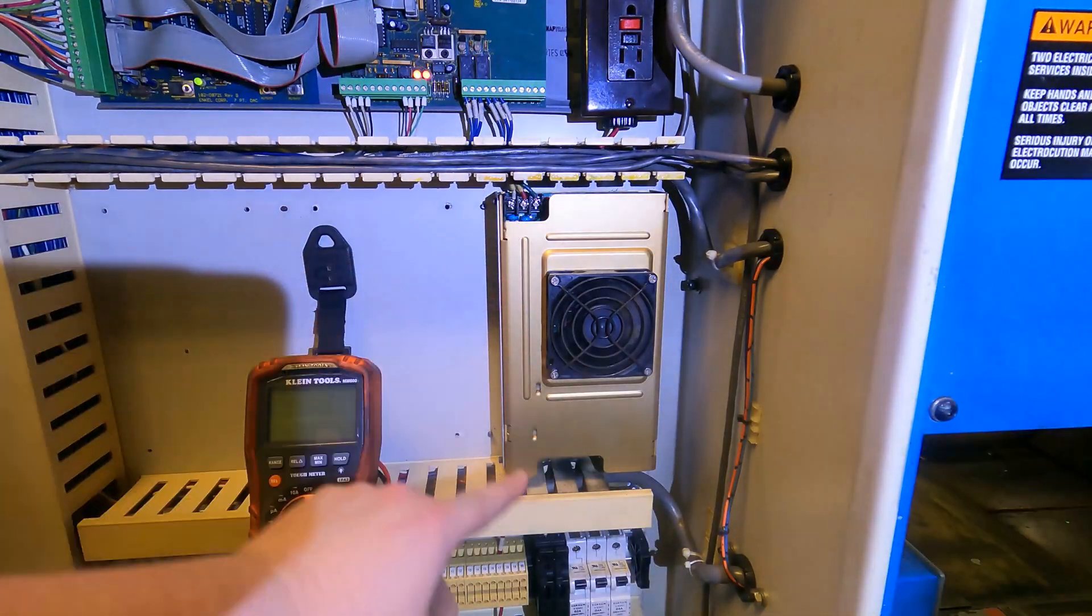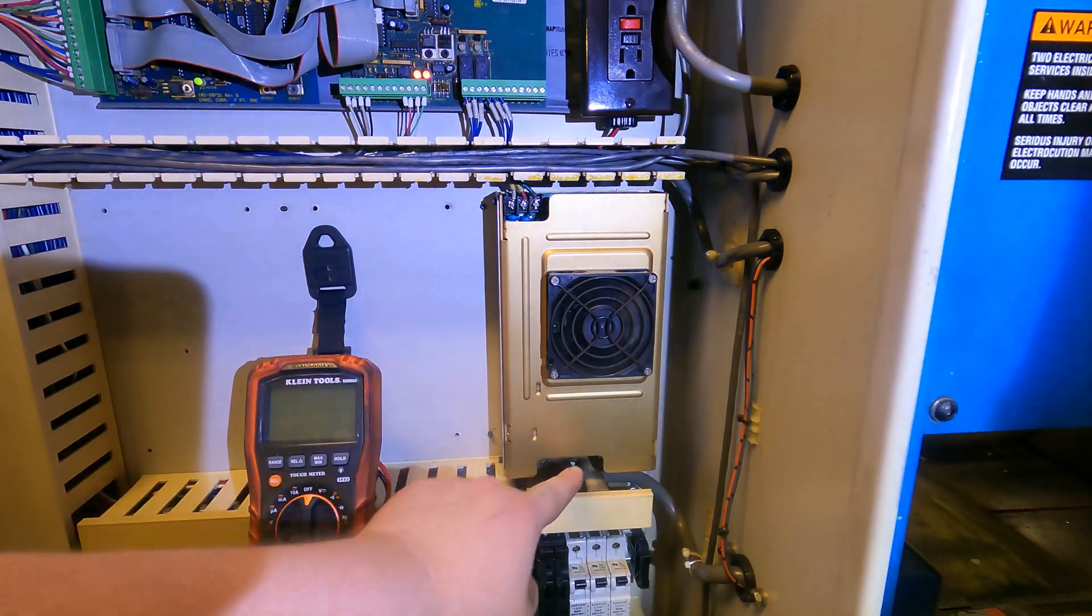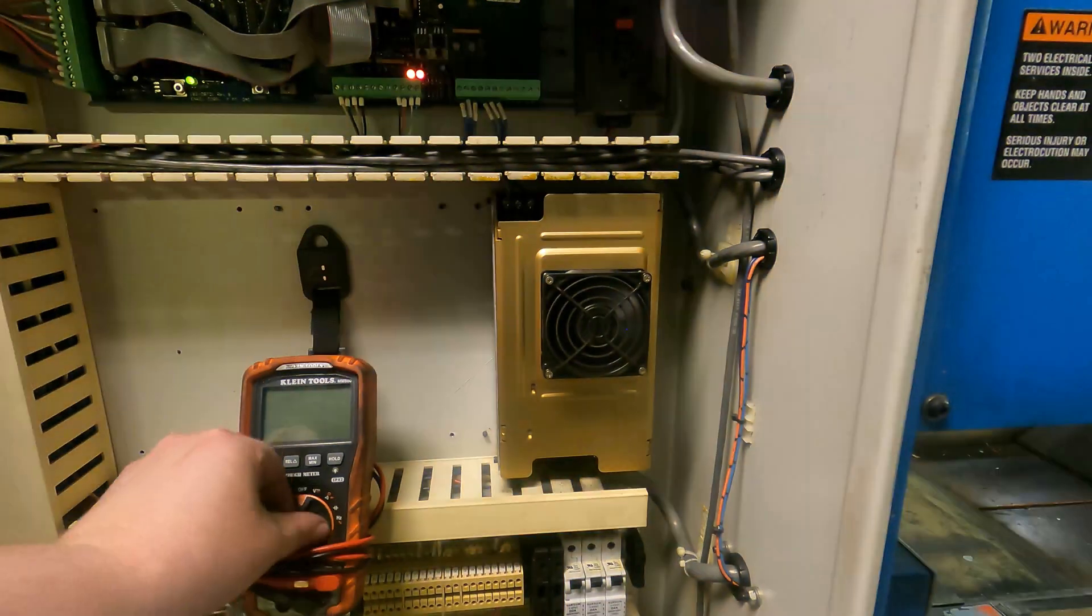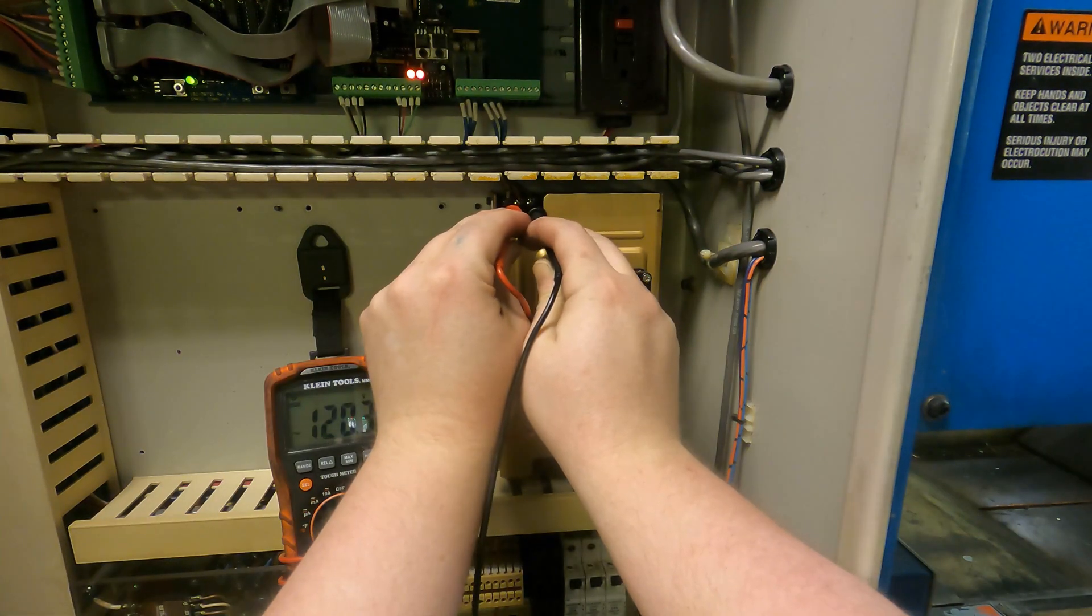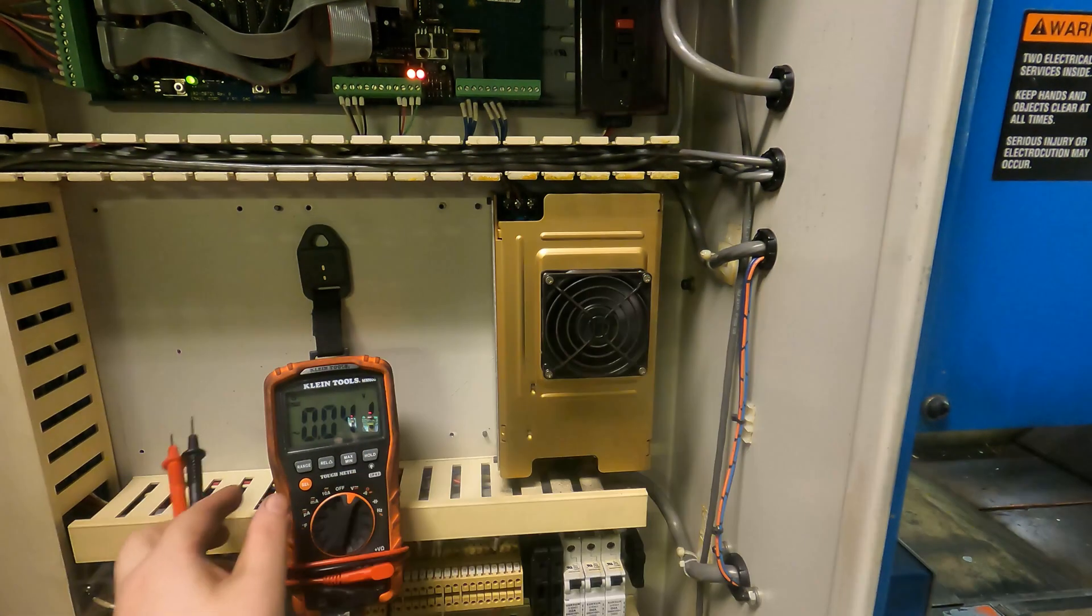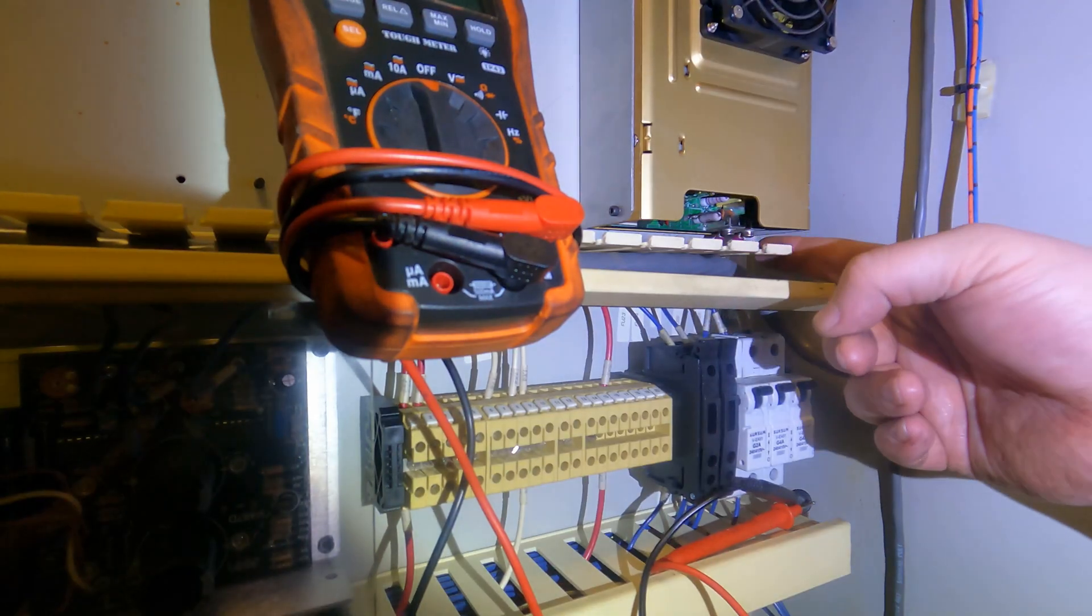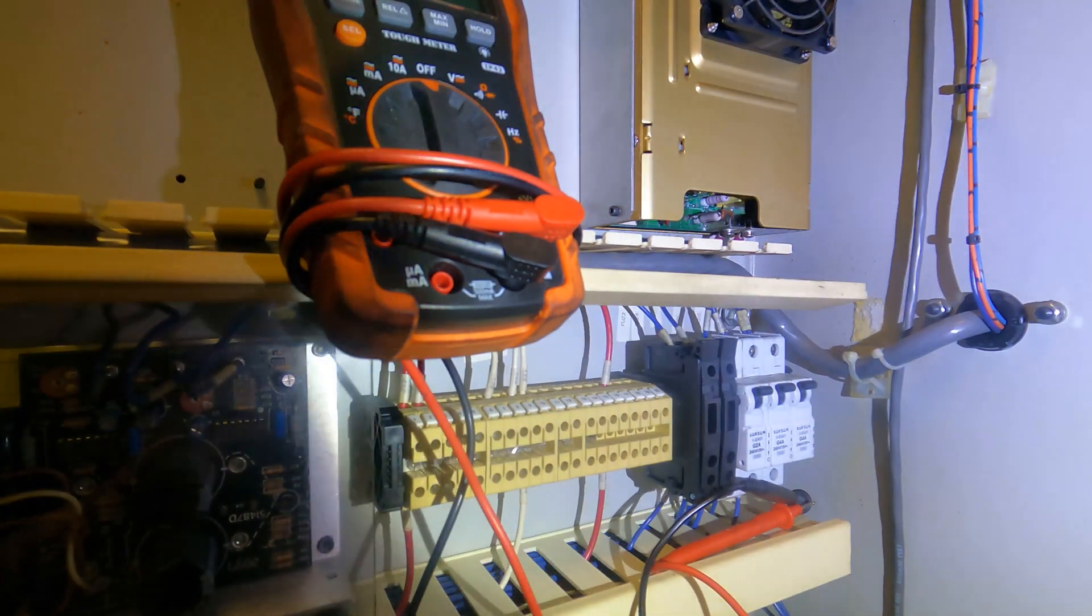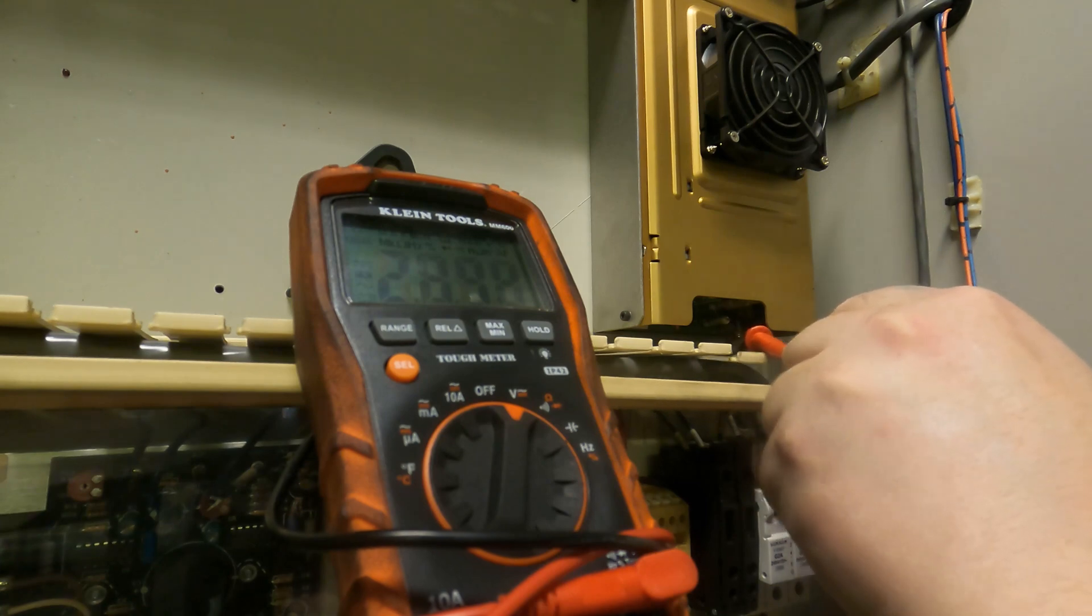So on the top there's three terminals and there's two more terminals in the bottom. The input is here and then the output is there. So the way that we check that. All right. So right there we're getting 120 volts. We know you have 120 volts coming in. If I change this to DC you can kind of see our two connection points right there on the bottom. So I'm seeing 24 volts DC going out.